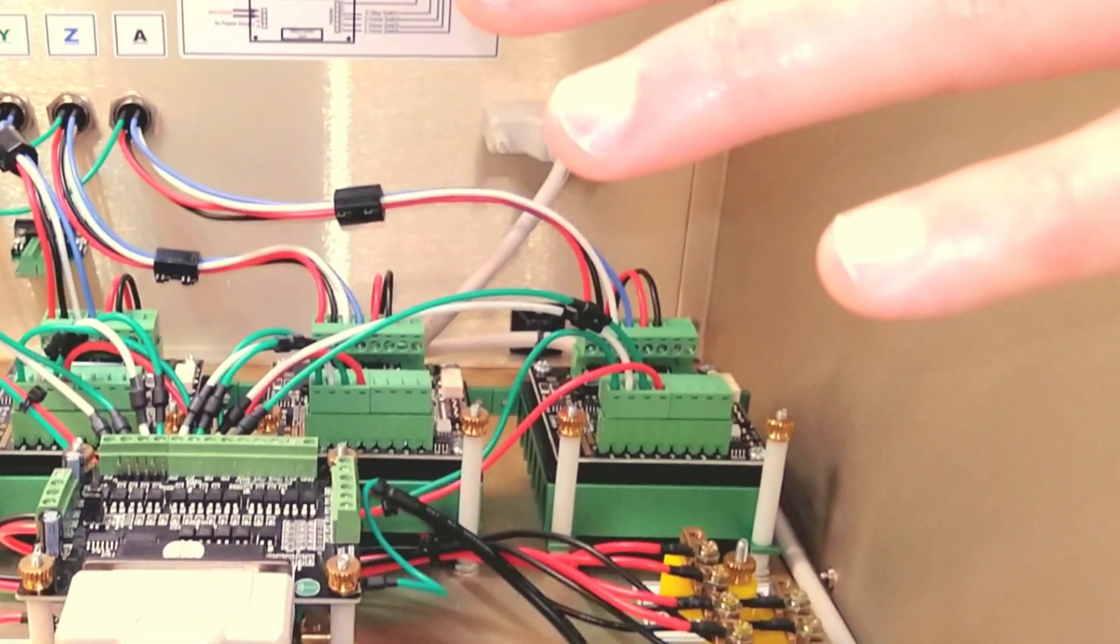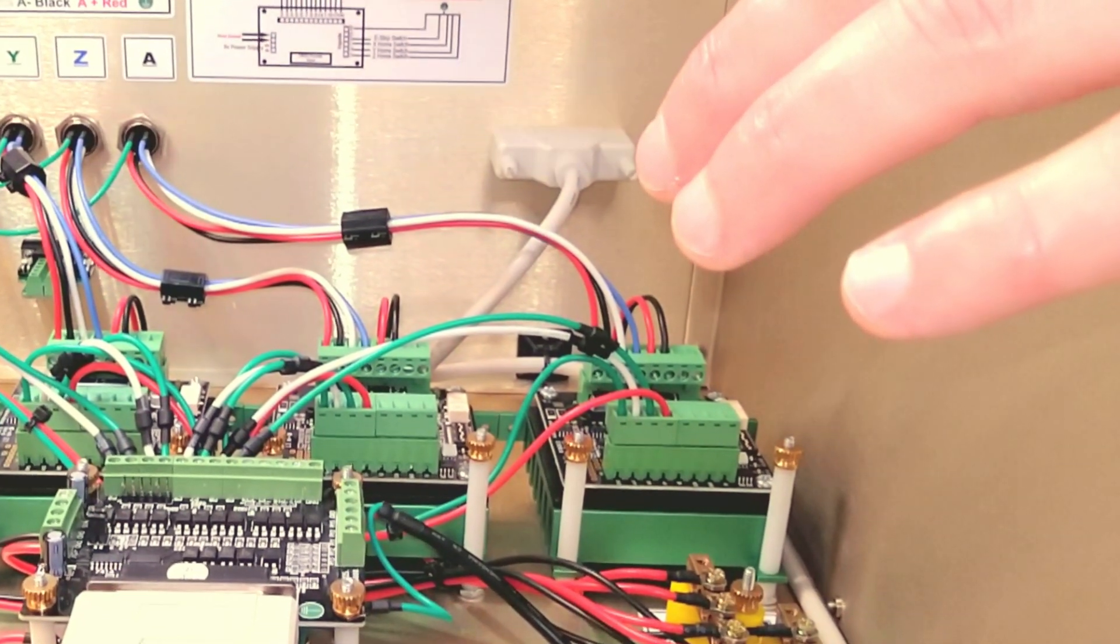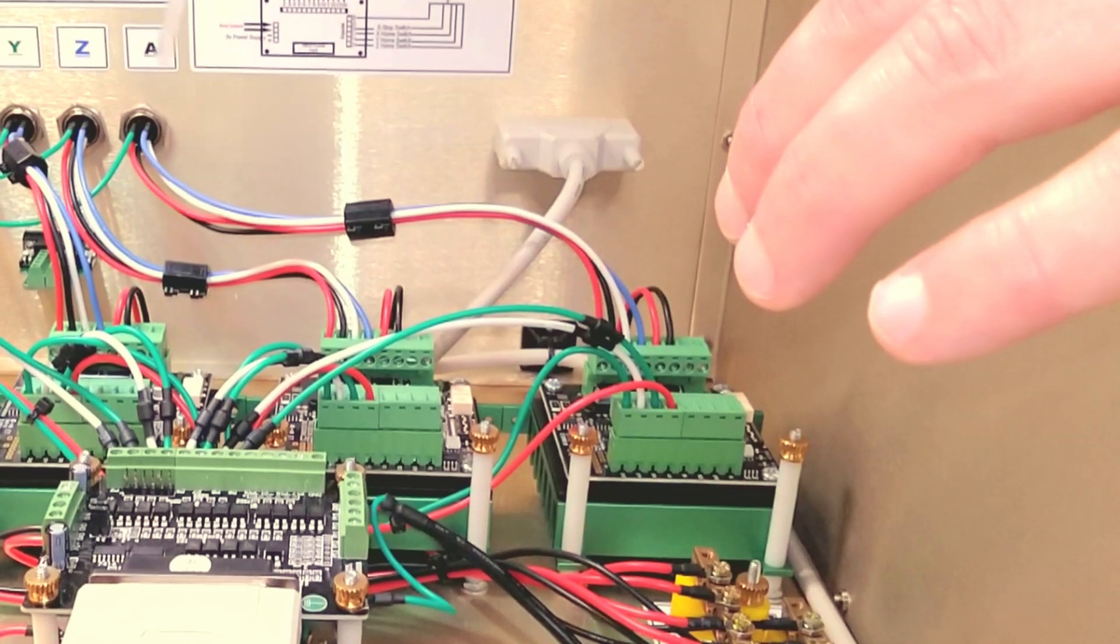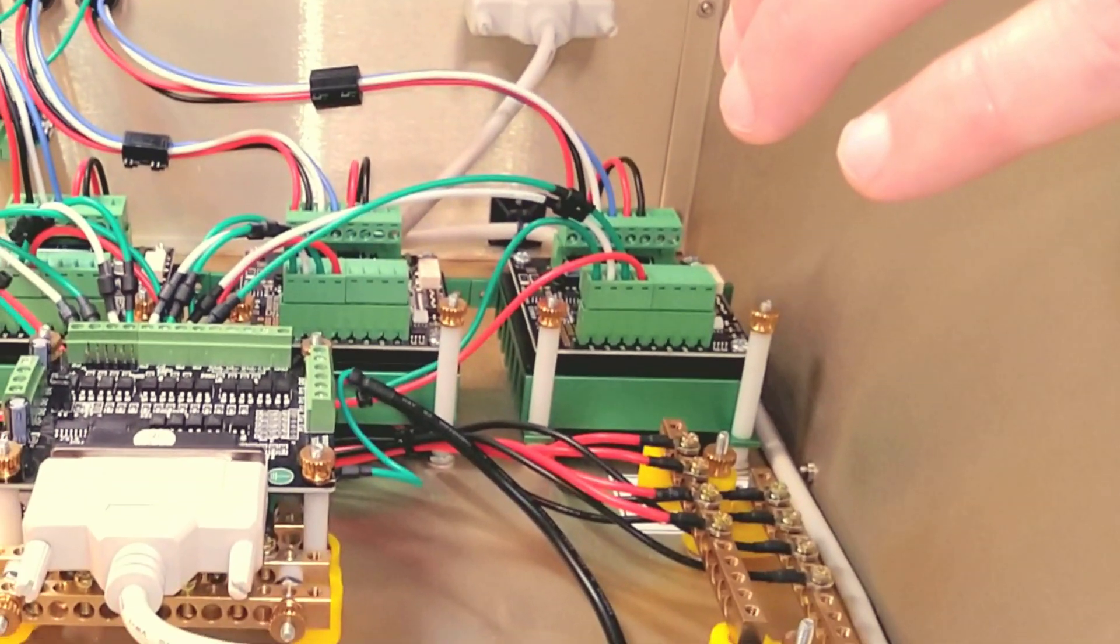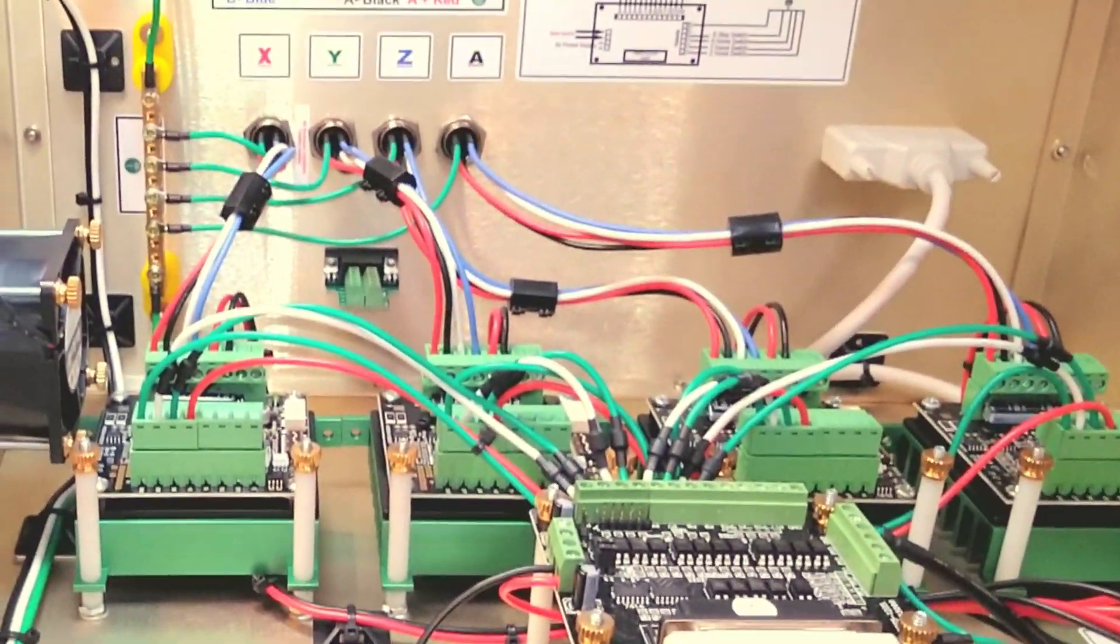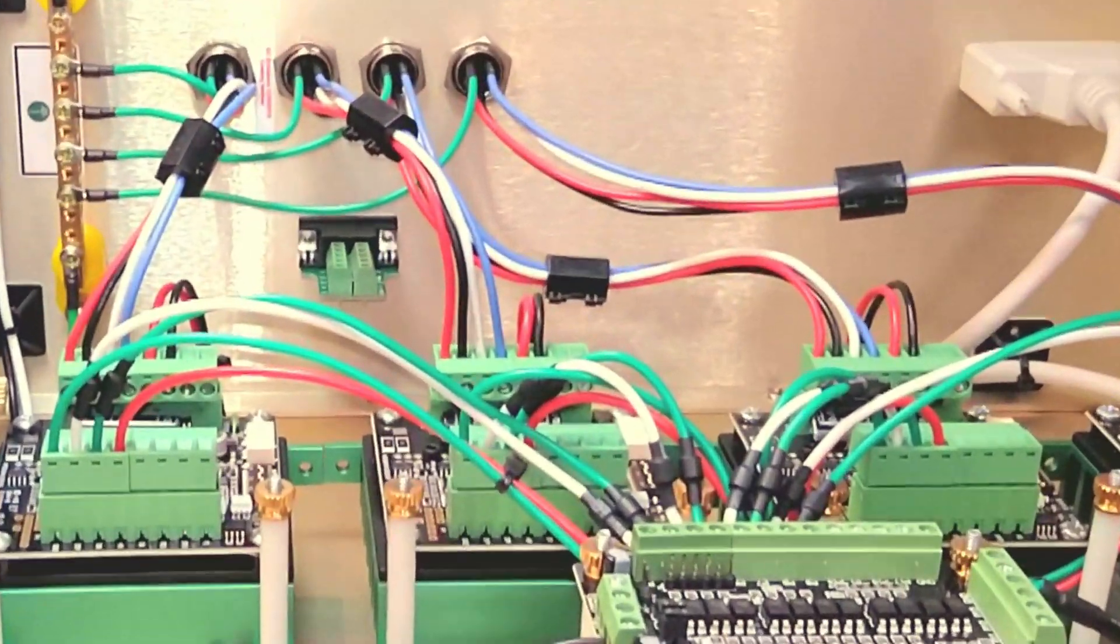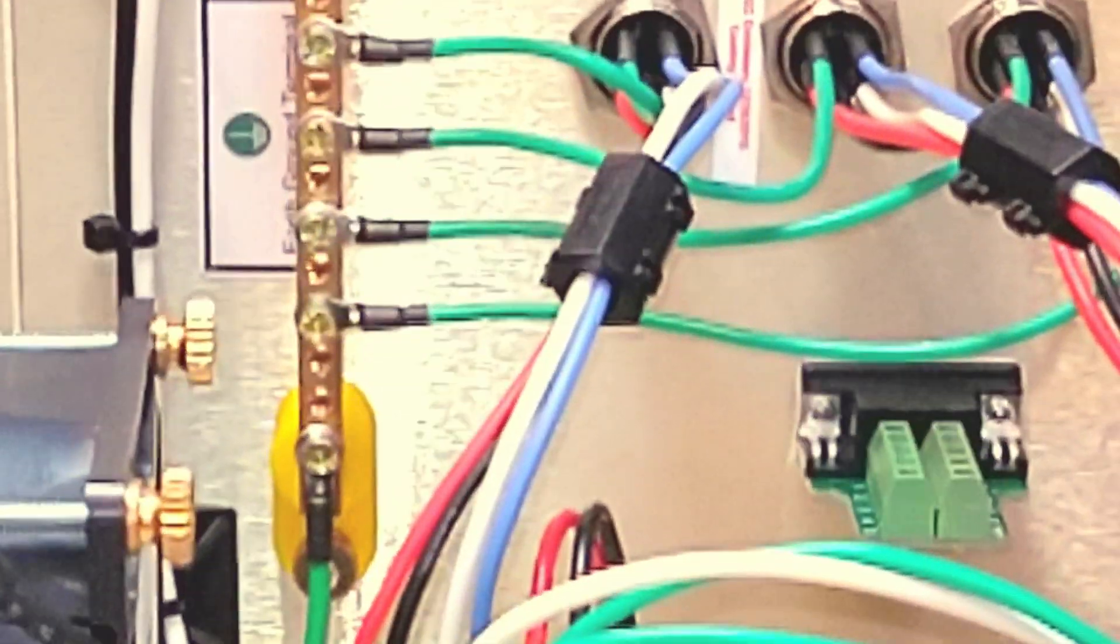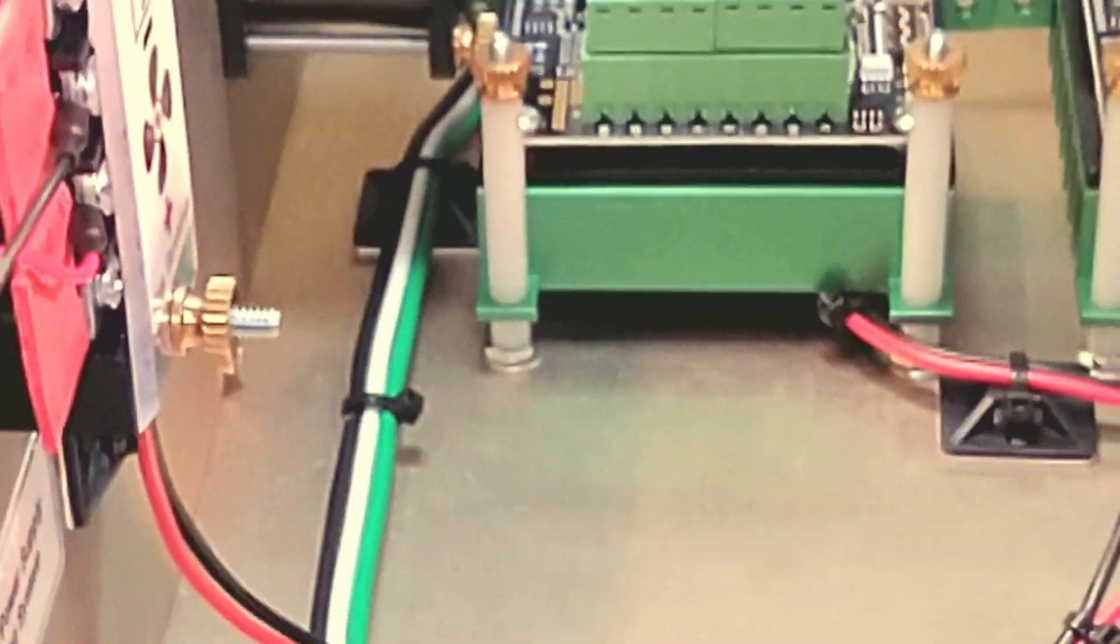None of these leads are in excess of 12 inches. They're all very small. With the dual ferrites, you mitigate basically all EMI without dealing with shielding, which is much cleaner. We've got our giant ferrites actually going around all of our leads to drive our motors. You can see all four of them right there. I get a lot of questions on the grounding as far as how a system is grounded. You can see our ground splitter right here. Ground comes into the system. Here's the shield drains coming right off of our GX-16 five-pin connectors. They go right in, so they're sharing the same central ground point, which would be known as a star point ground. Comes down, splits, and goes right over to our power distribution block for 110.